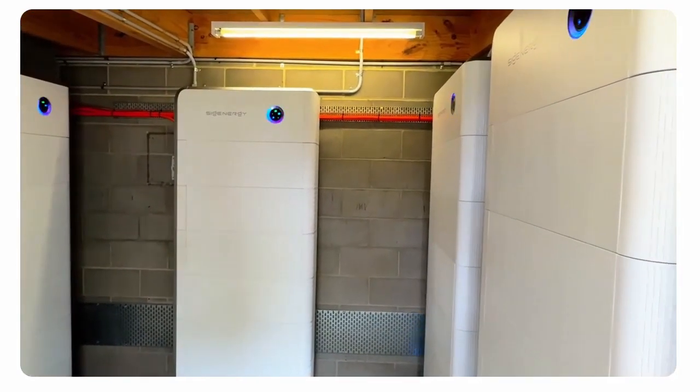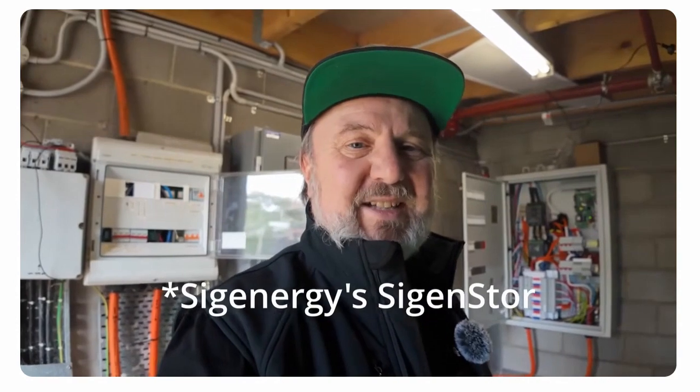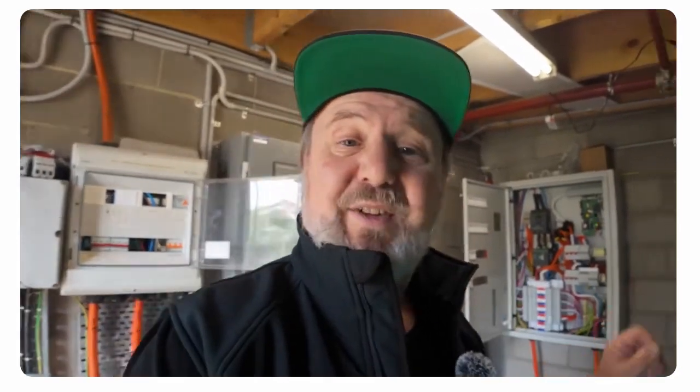Behind me is the gateway. The gateway is one of the kind of secret features of the SigenStor system — it can utilize a lot of parallel connected inverters. The gateway is the point where they all parallel through their own breakers, and there is a control system inside that controls the parallel link with other sources such as the grid or a generator. One of the really amazing features of the gateway is it can do zero millisecond UPS functionality.